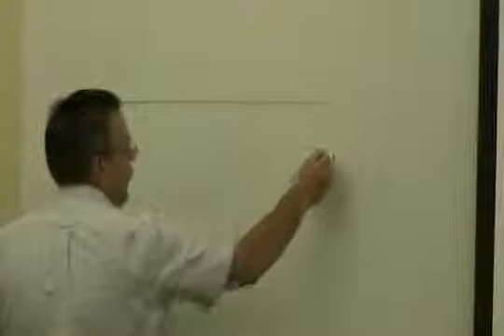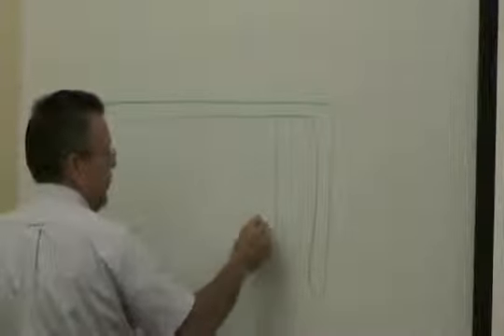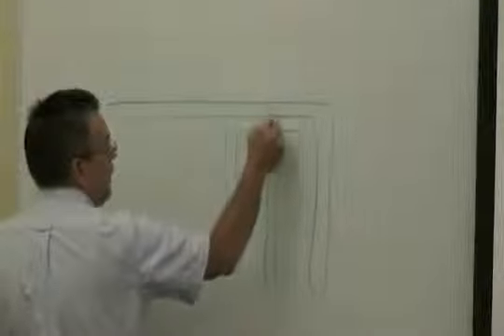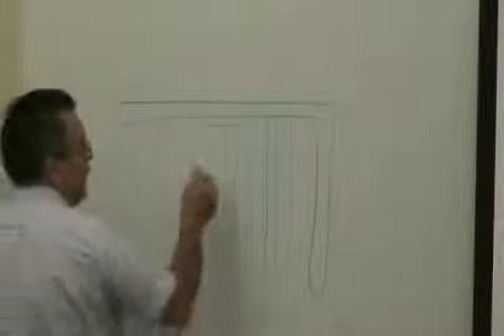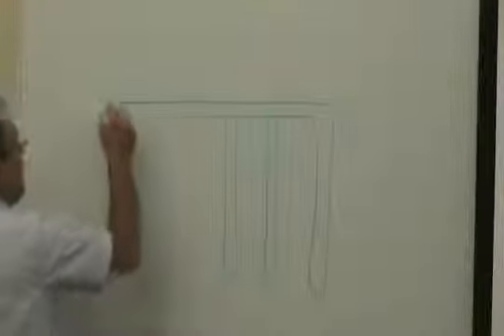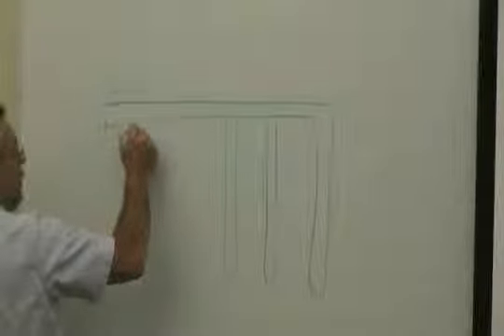Loop fields. You can have series and parallel loops. Most people, the loop field is, again, just another place to reject heat or absorb heat. When you come outside of the building, generally most people will drill holes in the ground and come back. These are called parallel loops. So all these loops are parallel. They come off the supply, they go right back into the return into your building. And the intent is, in the summertime, you're coming out here at 100 degrees and you're hoping to go back at 90 degrees, using the ground as a heat exchanger. In the wintertime, you're coming out here at probably 50 degrees and you're hoping to come back at maybe 60 degrees, an ideal loop. It gets colder than that if your loop's not working in the wintertime.